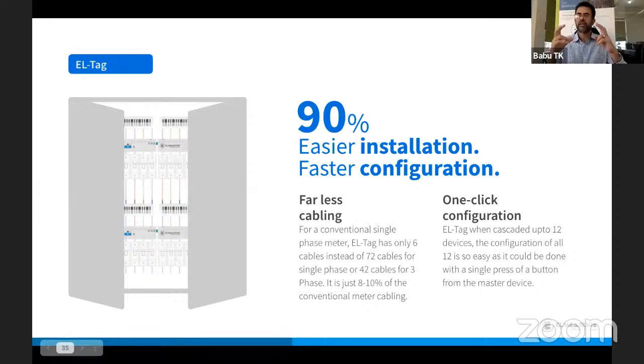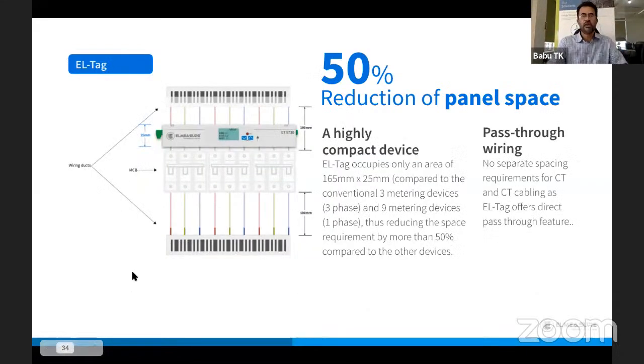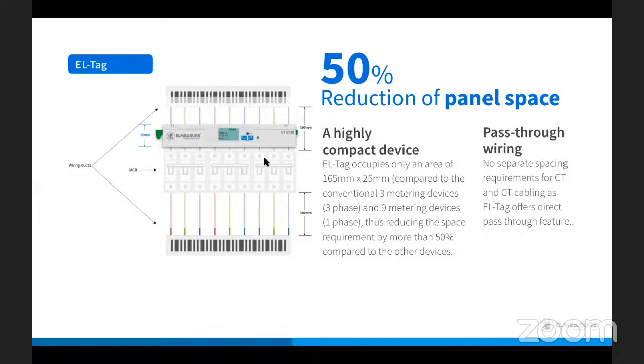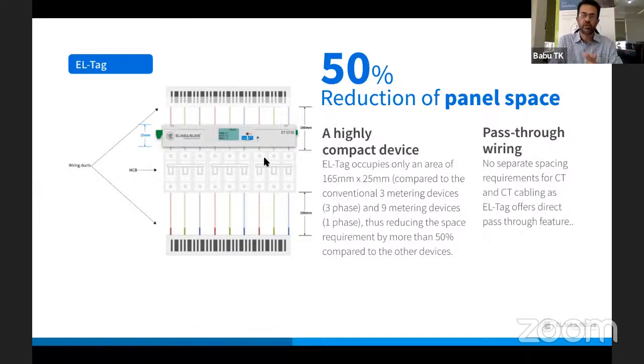Okay, I did not mention what happens if it is 4-pole. If it is 4-pole, you may have to connect only 2 of them, which is taking about 8 spaces. It has 9 holes. So 2 numbers of 4-pole MCB took 8 hole space, and 1 is empty. Now you could use it for 2, fine. The 4th wire could be neutral. You can also pass the neutral wire just like that. It measures the neutral. It has the capability of identifying the neutral connection or whichever phase it is. So it has auto detection of whether it is phase or neutral, it has that detection internally, and it stores the information. So even for 4-pole, absolutely no problem. You will have 1 extra hole left.